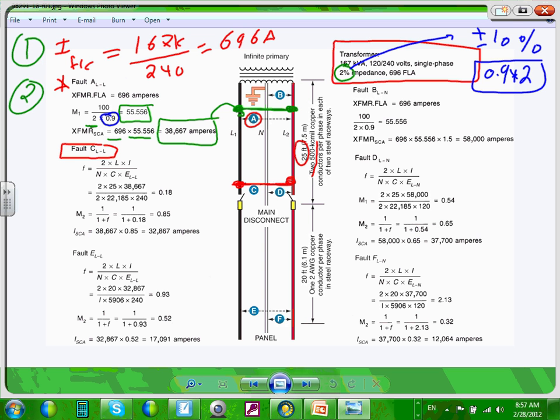Okay, so the new stuff that you need to know is there's a new formula. This formula is called F. For this single phase, F is equal to 2 times L times I divided by N times C times ELL, where L is the length, I is the current we found, N is the number of conductors in parallel, C is the factor for the conductor, we're going to find C, and ELL is the voltage line to line. So this is a formula. If you are to do it, bring the formula with you. Cool? The F factor, they call it.